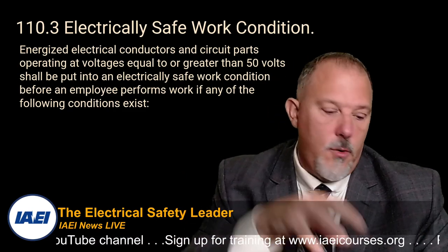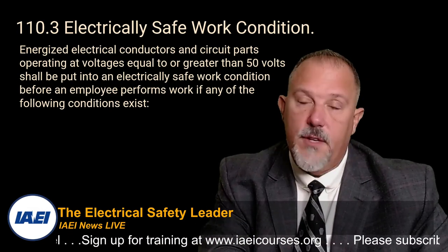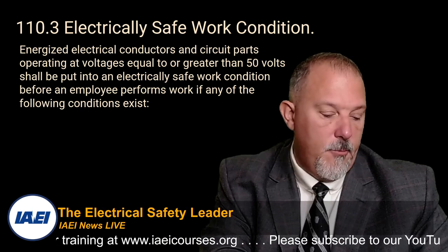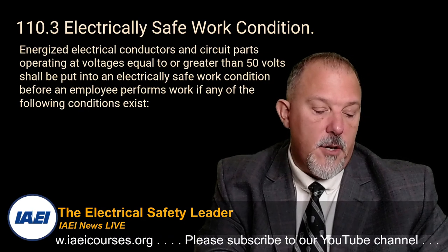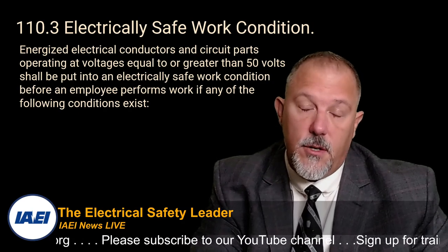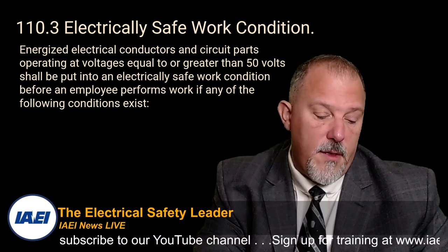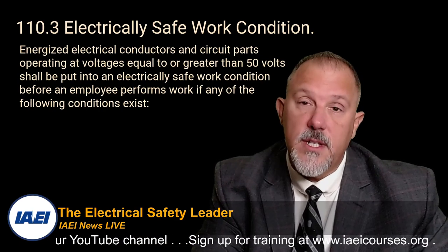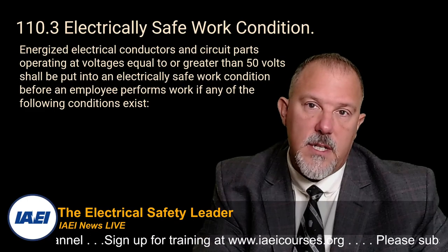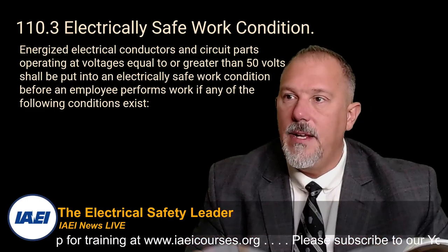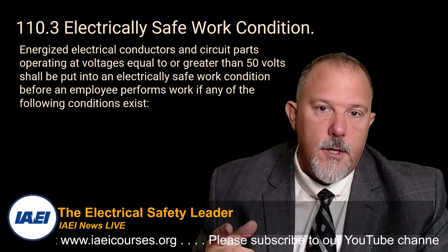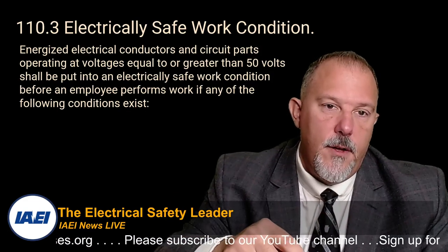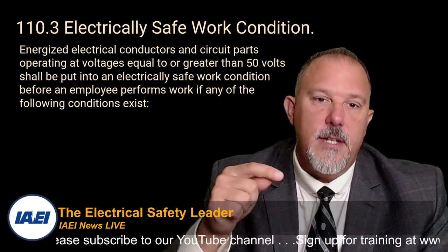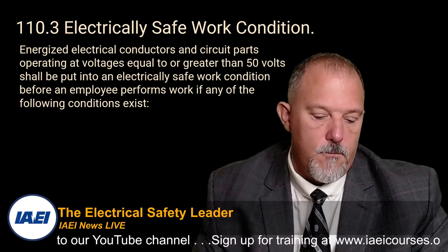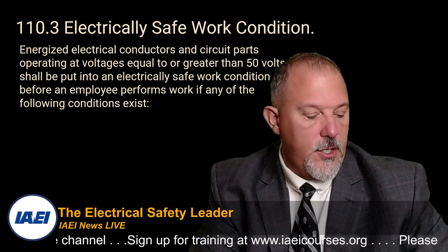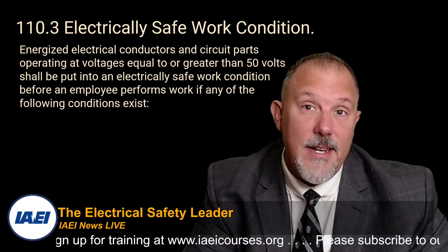And there are different distances. So for example, 120 volts. If you're operating at 120 volts, so in this table, 50 to 150 volts, your limited approach boundary for exposed fixed circuit parts, which I think is probably most of what we deal with, is 3 foot 6 inches. So if you're closer than 3 foot 6 inches, then 110.3 tells me that you need to put those conductors into an electrically safe work condition. 3 foot 6. In fact, 3 foot 6 is good all the way up to 750 volts. So that's a key number. That's a key measurement for you.